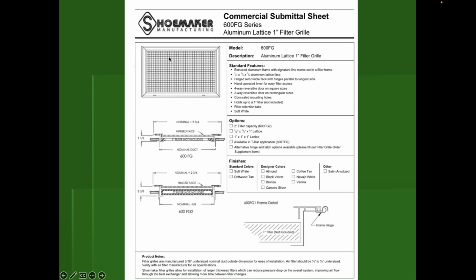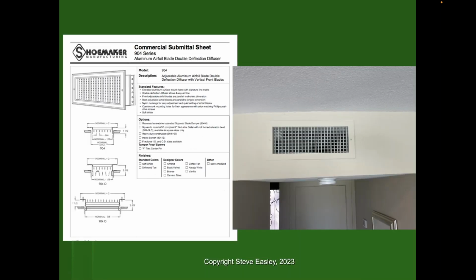I'm a big believer that you use commercial grade grills. These are egg crate grills that you can get up to 2 inches thick, so you can put pleated MERV 13 filters in, which filter 85% of all the particles that are less than a few microns, which are really good in terms of enhancing the indoor air quality of your house without creating great pressure drops.